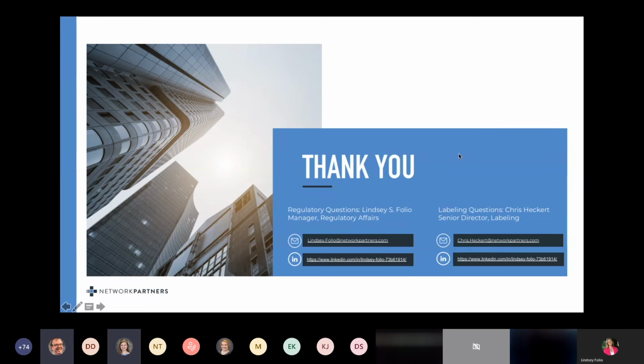Any guidance or tips regarding the FDA requirements for a symbols glossary would be helpful as far as incorporating the EU MDR requirements and translations. So I tried to turn it into a question asking if we had any guidance or tips regarding those FDA requirements. Okay, the FDA requirements to identify any symbology that you're using on your package that isn't supported with English language would be just to put that symbols glossary in your IFU.